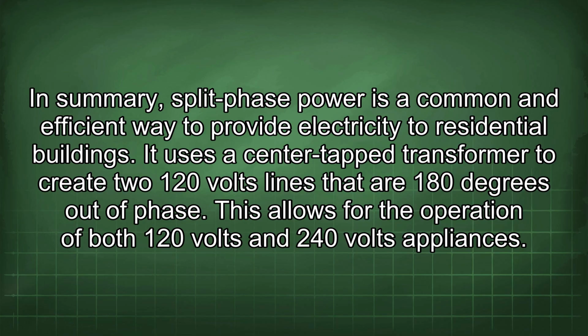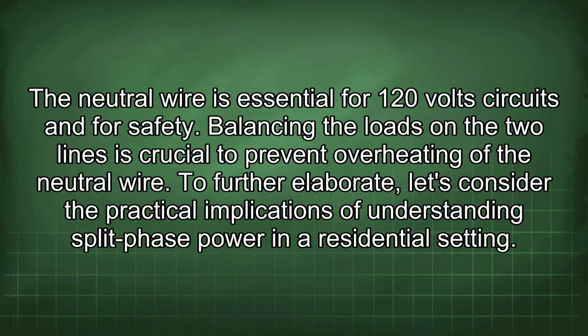It uses a center tap transformer to create two 120 volts lines that are 180 degrees out of phase. This allows for the operation of both 120 volts and 240 volts appliances. The neutral wire is essential for 120 volt circuits and for safety. Balancing the loads on the two lines is crucial to prevent overheating of the neutral wire.